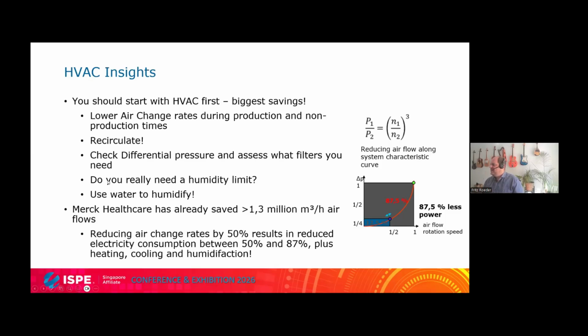Humidity limit also brings a lot. You can turn it down, or look at the specification. That is very, very interesting. Do you really need a humidity limit? Let me imagine you have a warehouse and you store hermetically closed product in drums that are really closed, where no air can go inside. Then temperature still has an impact, so you need to control temperature in the warehouse, but humidity not. So you could say in the warehouse, if all product is closed, you don't have a humidity spec and don't need to humidify or dehumidify. And this saves a lot.